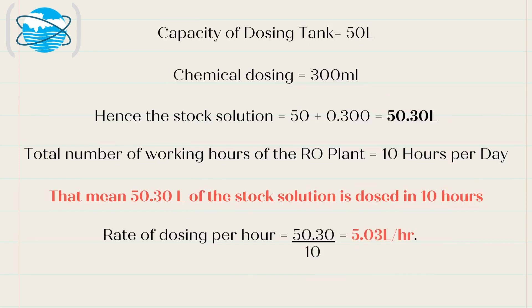How to set the rate of dosing per hour: if the capacity of the dosing tank is 50 liters and the chemical dosing is calculated as 300 milliliters, then the stock solution will be 50 plus 0.300 equals 50.30 liters. As the total number of working hours of the RO plant is 10 hours per day, that means 50.30 liters of the stock solution is dosed in 10 hours. Hence the rate of dosing per hour will be 5.03 liters per hour.